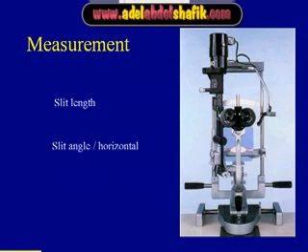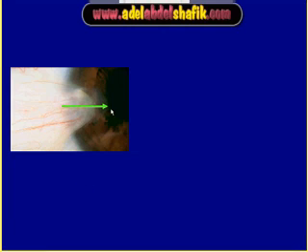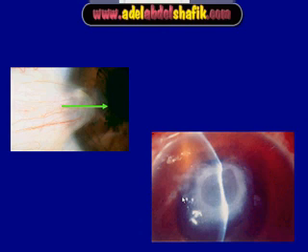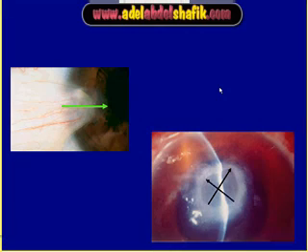The slit lamp can be used for measurement. We can know exactly the length of the slit light and also the angle of the slit light from the horizontal compared to the vertical meridian. For example, if there is a foreign body you can tell exactly how many millimeters it is into the cornea. If you get a corneal ulcer and you are following the patient, you can measure the two axes of the ulcer in millimeters, so during follow-up you can tell whether the ulcer is improving or not.